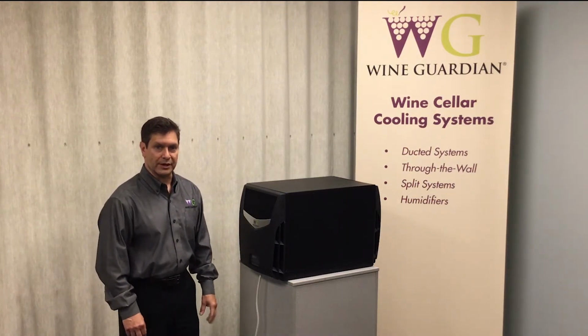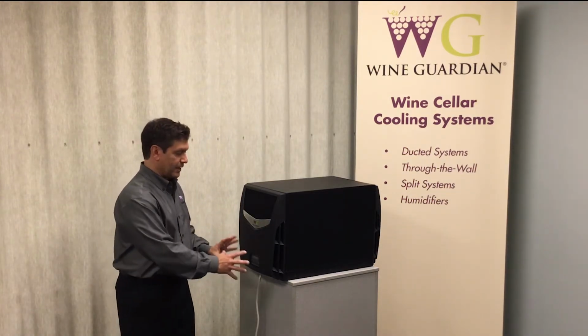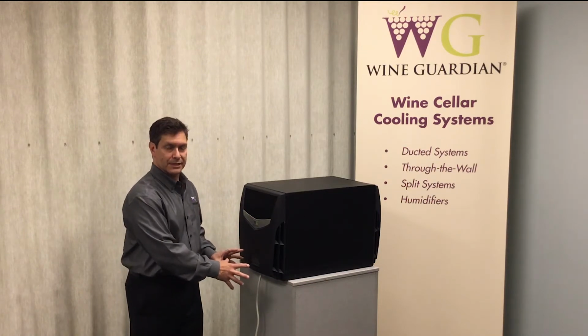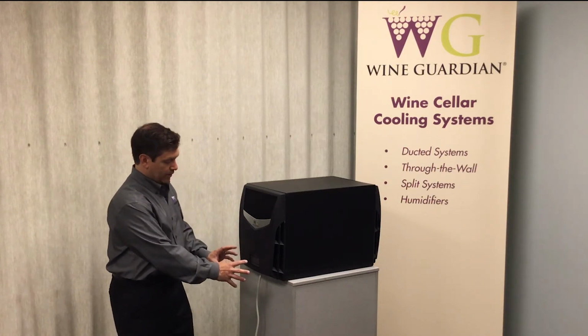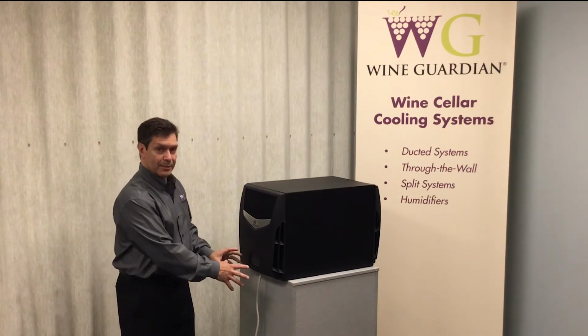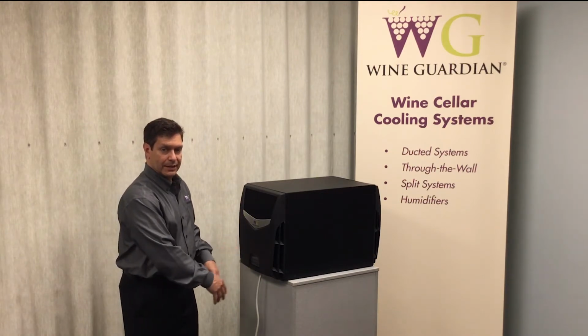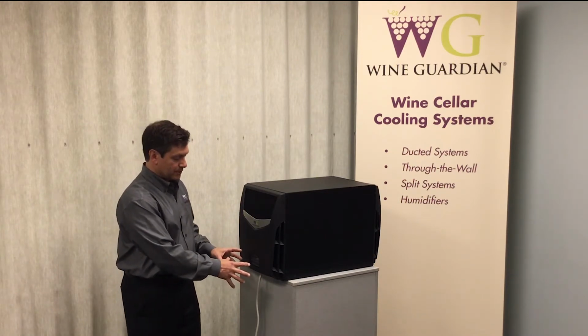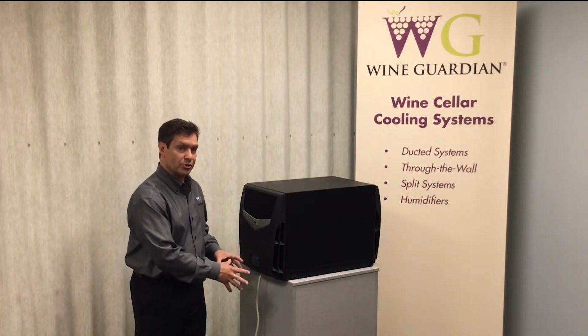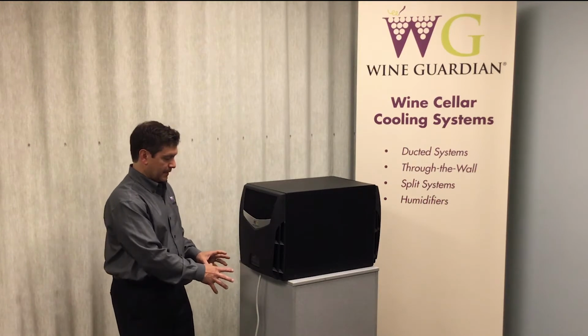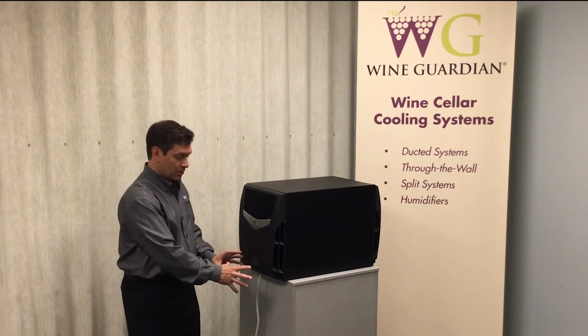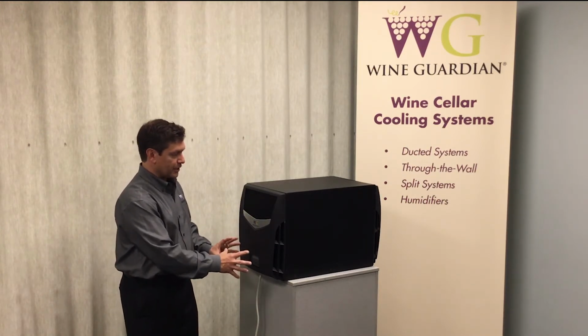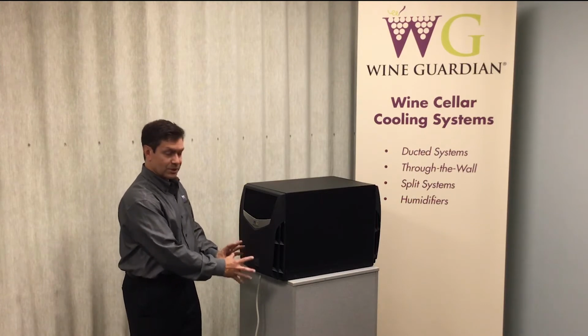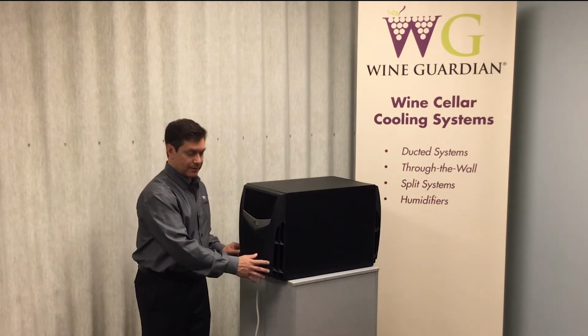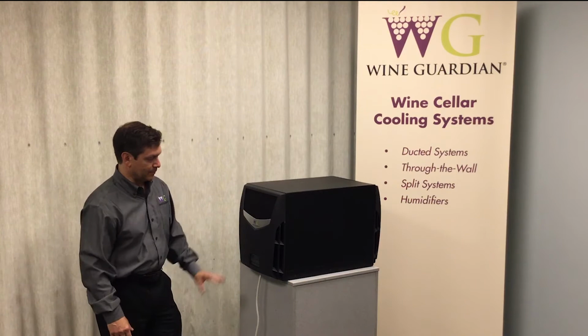The controls for the unit are all centrally located right here on the front face of the system. So this is where you will display your temperature and humidity, where you can adjust your temperature and also control your humidity if you had one of our optional humidifiers. This is where you might see any alarms. All of the functioning of the system itself happens right here at the main control panel on the system.